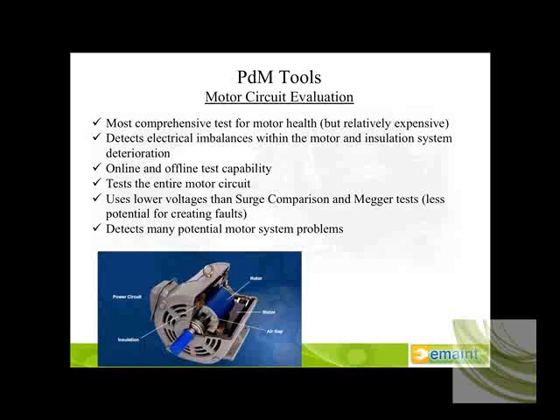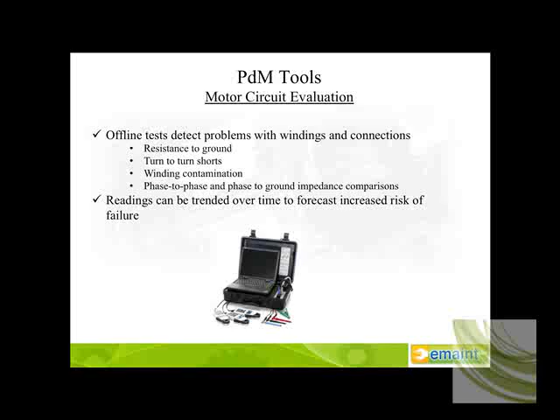So in looking at online testing with motor circuit evaluation: loose or broken rotor bars, cracked end rings, misalignment, power harmonics issues, voltage imbalances, under or over voltages. And then in the case of offline testing: resistance to ground, turn-to-turn shorts, winding contamination, phase-to-phase and phase-to-ground impedances, and comparisons. And then also the readings with these instruments can be trended over time to forecast any increased risk of failures. A couple of very, very good tools to add to the top three.